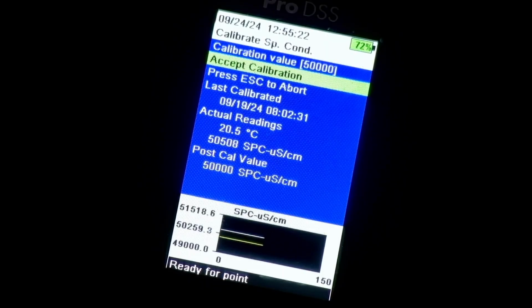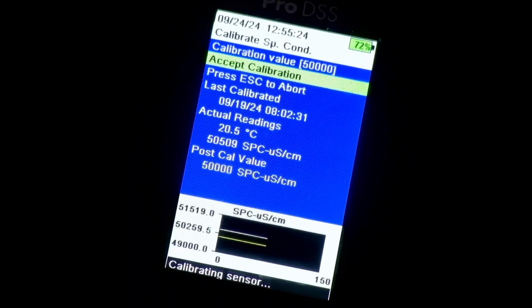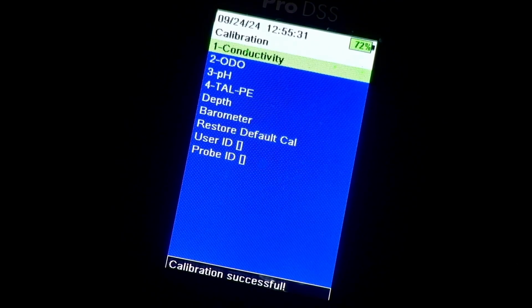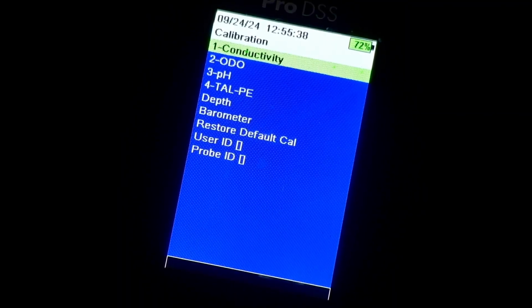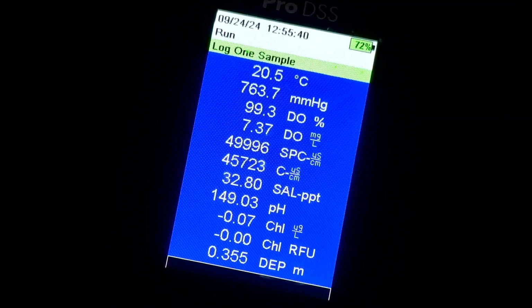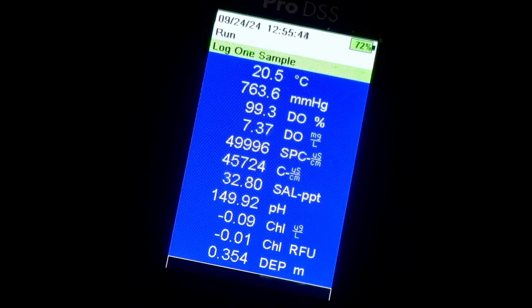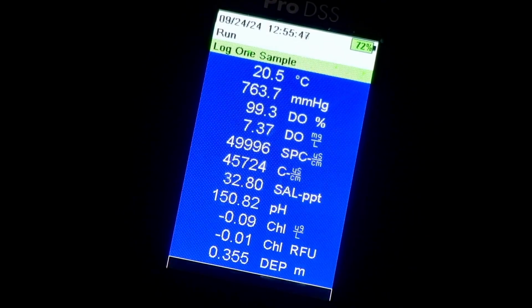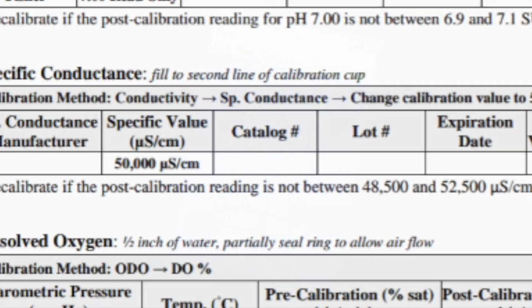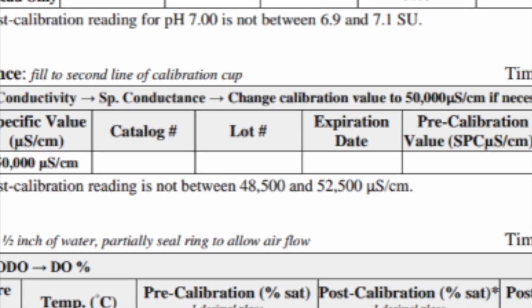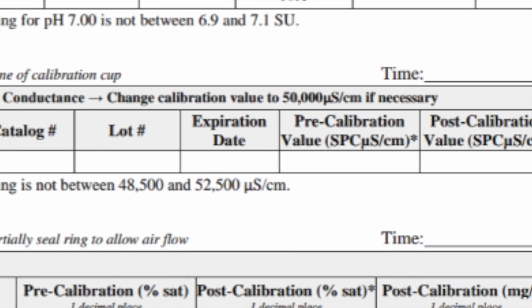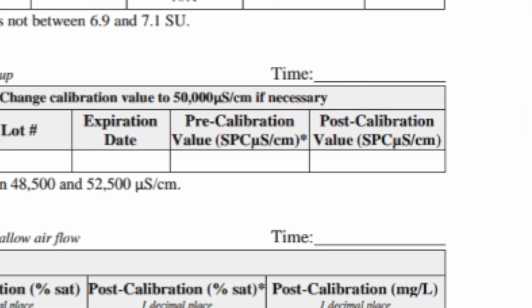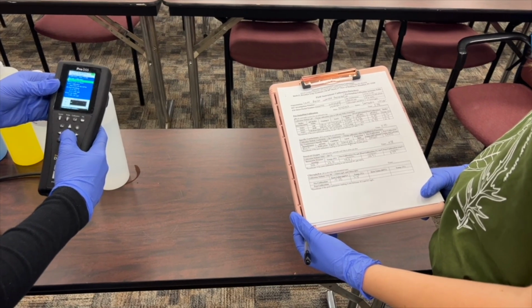After you're done, select Accept Calibration, and the message at the bottom of the screen should read Calibrating Sensor. Once complete, the message Calibration Successful will be displayed again and the screen will return to the calibration menu. Press Escape to return to the home page to read temperature and the SPC value and record it on the calibration sheet under post-calibration concentration. The post-cal value must read between 49,500 to 50,500. If the reading is not within this range, you will need to discard the calibrant, rinse the sensors, and recalibrate.